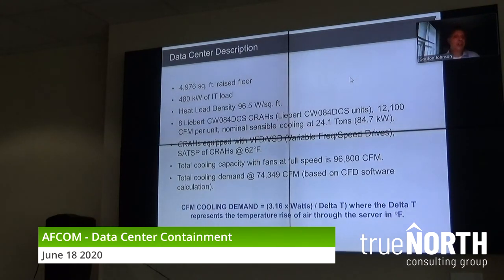Here's kind of an interesting thing. I'm giving this data center 96,800 CFM. That last bullet point, and again, this is another half hour, hour discussion, so I won't deviate too much, says the demand of the IT is 74,000 CFM. Where did I get this number? The simplest answer is the CFD software makes certain assumptions, and that's how it comes up with the IT demand. I can hard code that number in.